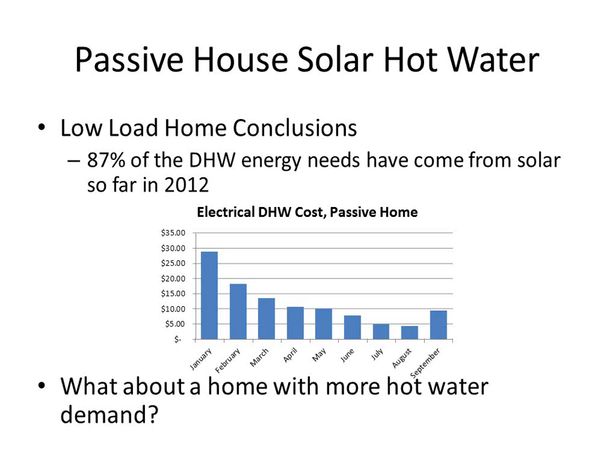When I went back and looked at the photograph of the system I borrowed from Peter's past home presentation, I realized the system was installed with 2 mixing valves — one on the output of the solar hot water storage tank, and one on the output of the electric hot water tank. One thing we've learned with monitoring is that level of tempering isn't necessary and is unproductive. So one recommendation we'll make is to remove that intermediate mixing valve — as long as you have a functioning mixing valve on the output of your backup hot water heater, there's no need for that second one.